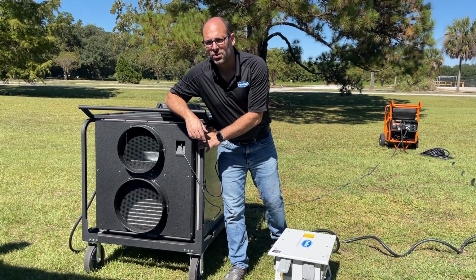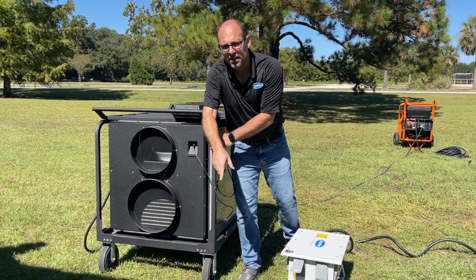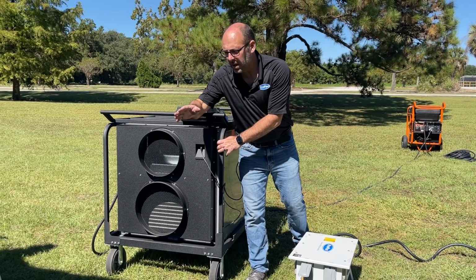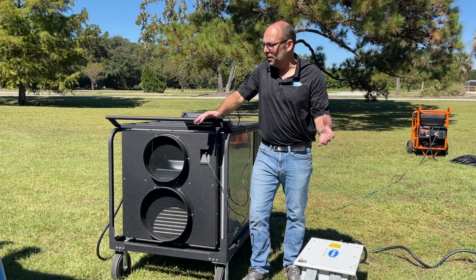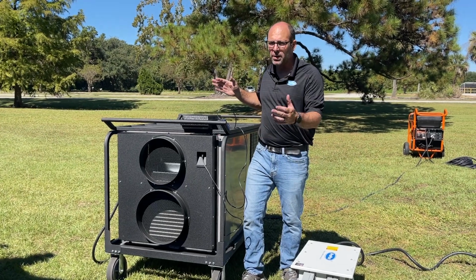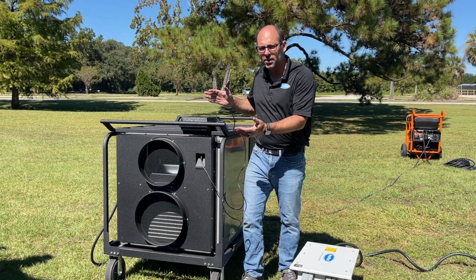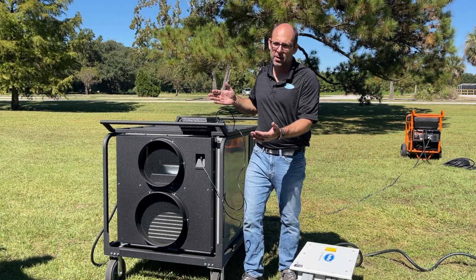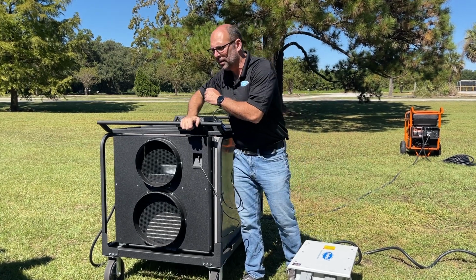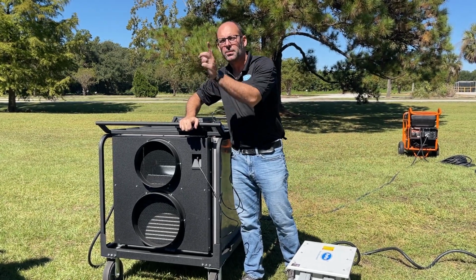So we're going to go ahead and attach the plenum to the ducts. A word of note: make sure the lines are as straight as possible, and that there's no back pressure placed onto the HVAC unit, as it might cause it to freeze up in warm temperatures. This also allows good airflow into the plenum itself.